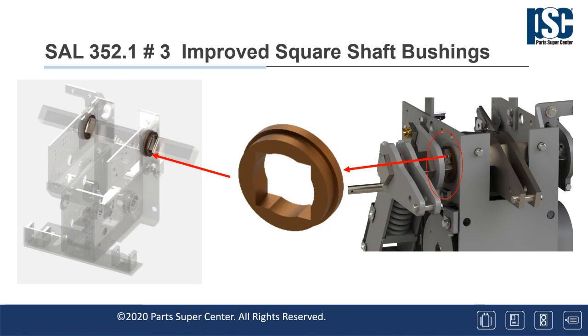The modification involves removing the 2 cast iron bushings from the 2-inch square shaft and replacing with 2 bronze bushings as shown on the right side of this slide and in the center. Cracked cast iron bushings have been attributed to slow and sluggish breaker operation in a number of instances. Ordering information, again, will be included in the service advisory that accompanies these slides.